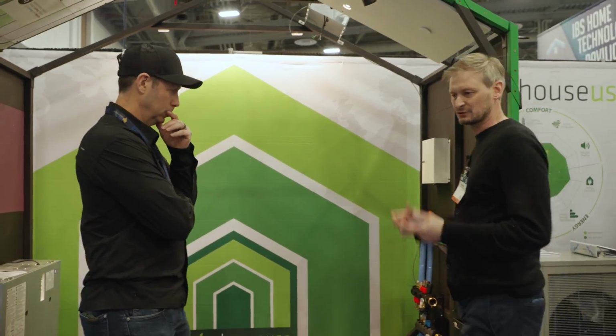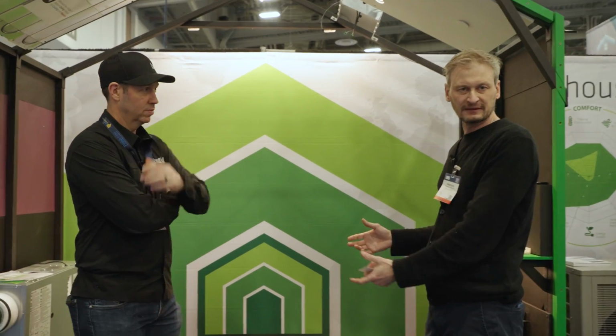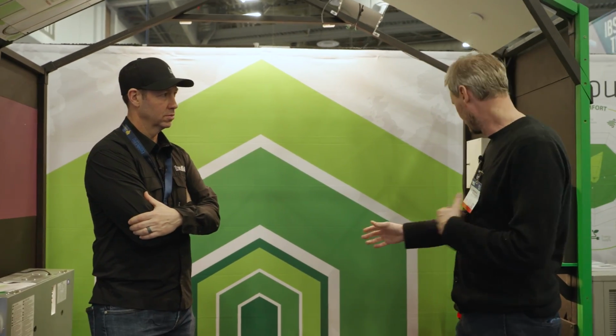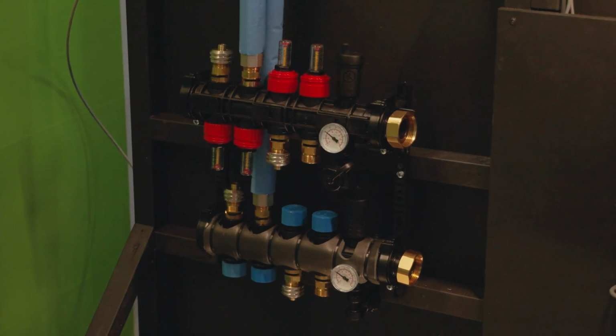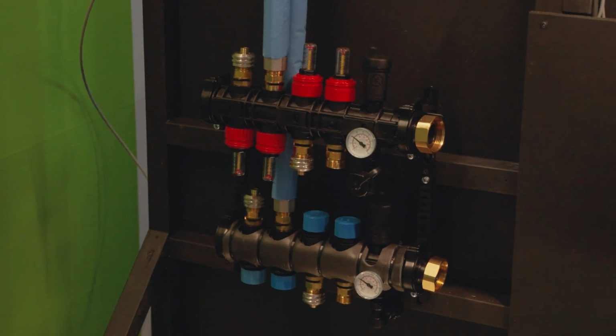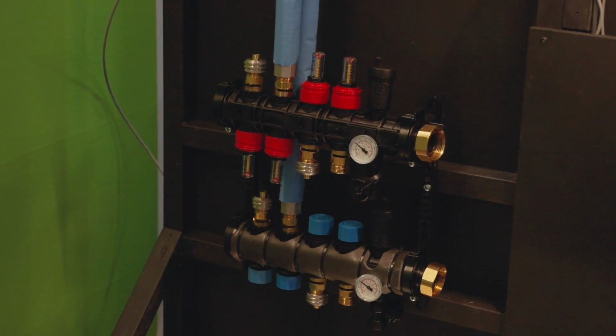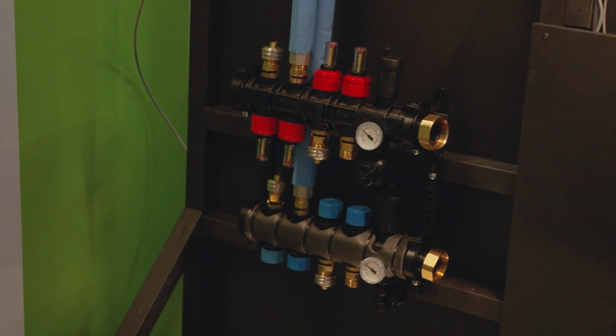Perfect, you have two lines, supply and return, going to a small buffer tank. From the buffer tank it's going to a manifold. Okay, so inside the manifold is chilled water. What kind of temperature are we talking about for chilled water? Is that 50 degrees, 30 degrees? Could be between 46 to 55 degrees.